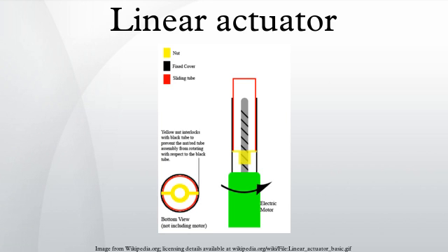For electromechanical linear actuators used in laboratory instrumentation, robotics, optical and laser equipment, or XY tables, fine resolution in the micron range and high accuracy may require the use of a fractional horsepower stepper motor linear actuator with a fine pitch lead screw. There are many variations in the electromechanical linear actuator system. It is critical to understand the design requirements and application constraints to know which one would be best.